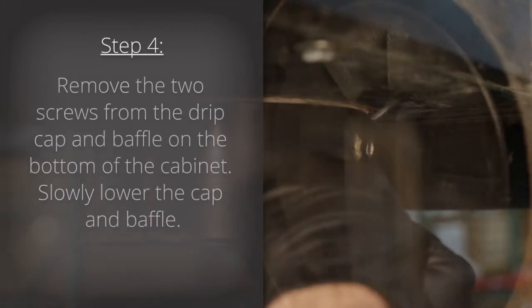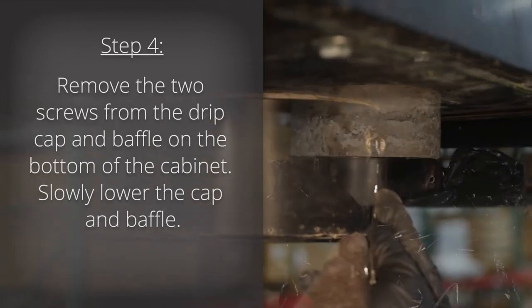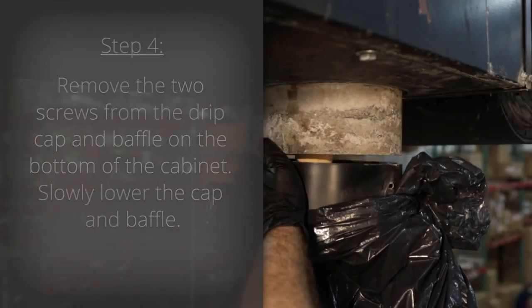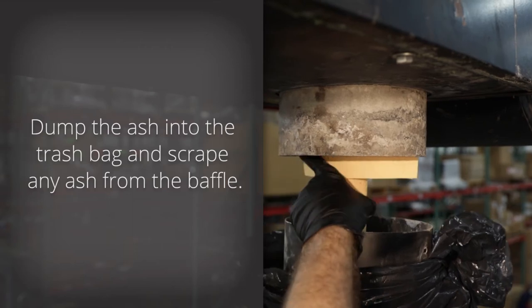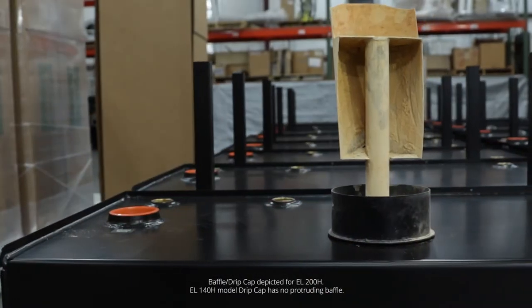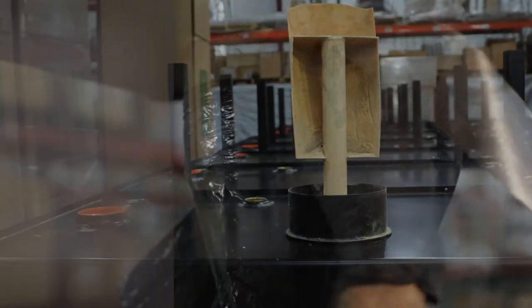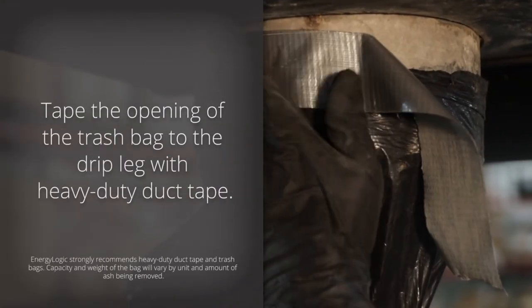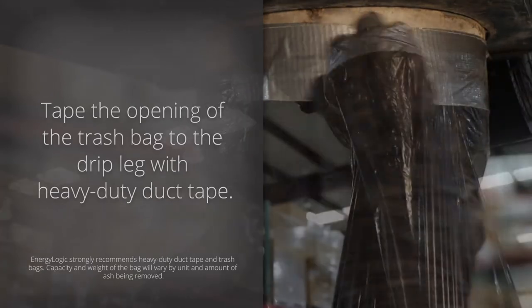Step four, remove the two screws from the drip cap and baffle on the bottom of the cabinet. Slowly lower the cap and baffle. Dump the ash into the trash bag and scrape any ash from the baffle. Then tape the opening of the trash bag to the drip leg with heavy duty duct tape so ash will be contained in the trash bag.